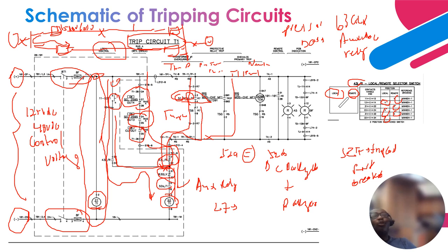That is if there should be a fault on this line. Right? So that relay, if a transmission line relay that is protecting both ends of the transmission line, one is located here, one is located here. That should be able to trip this circuit breaker, and that is perfectly true, right? So the output of that transmission line relay has to be asserted, right? The trip output contact right here has to change state from normally open to normally closed to be able to trip this breaker, okay?